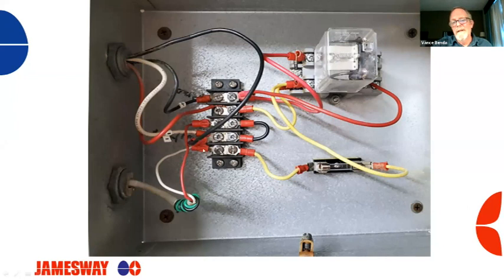So let's talk about the alarm loop. Here you can see in these three terminals, terminal 3, 4, and 5 are negative terminals. Here's your negative power supply wires connected to 4. 4 is jumpered to 3. Here's your alarm loop connection going out. Here's your alarm loop connection returning. If a sufficient voltage makes it back to this terminal, it goes through your quarter amp fuse, goes up here to terminal A, and latches this relay and silences your horn. As soon as you take that voltage away, this relay falls out, your horn starts blowing. And all that is part of the fail-safe system. This system is pretty good.